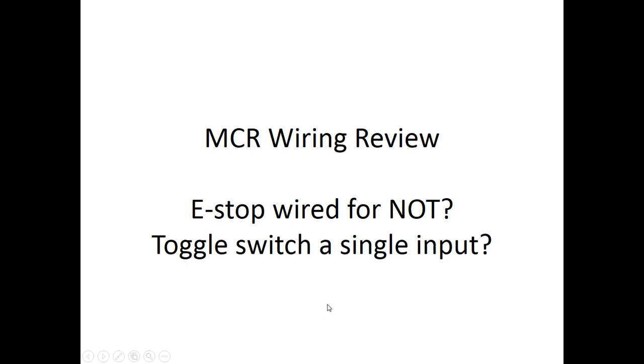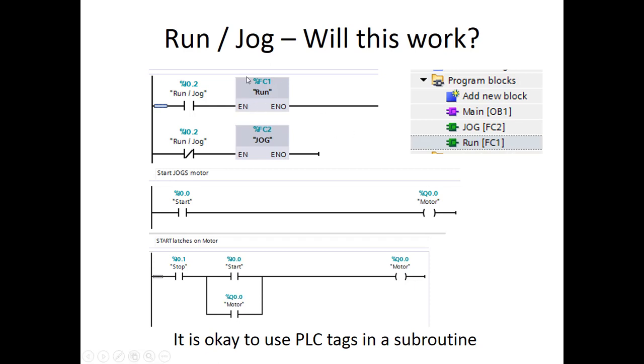For our run-jog examples there were a variety we'll be looking at. We had our e-stop, and our program was wired for a NOT. I want to remind you that you don't need to put a NOT on your e-stop because the e-stop is wired normally closed. If the e-stop was wired normally open, then you might use a NOT, but that's really not the correct application. You would wire the e-stop normally closed and then you wouldn't need a NOT. A toggle switch is a single pole that can switch between input one or input two, but we were using it as a single input — so the toggle switch would either be true or false.